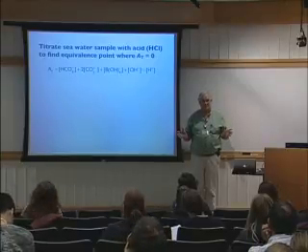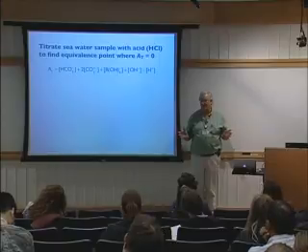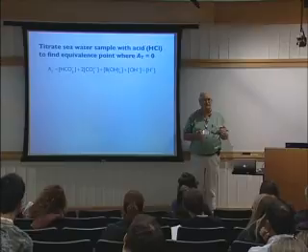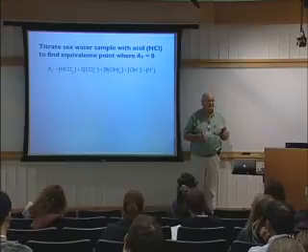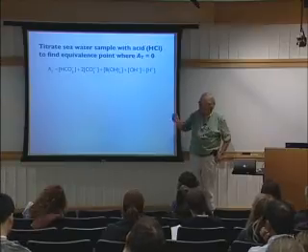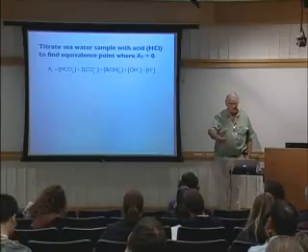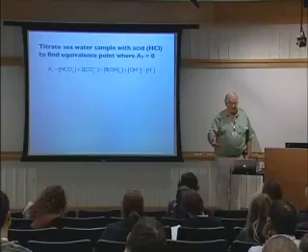That's not so good for sodium. But here, a negative alkalinity means you've got excess acid. So what you're doing with the titration is trying to get to the point: how much acid does it take to get that to 0?